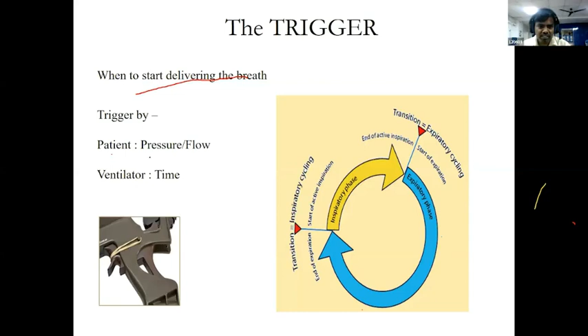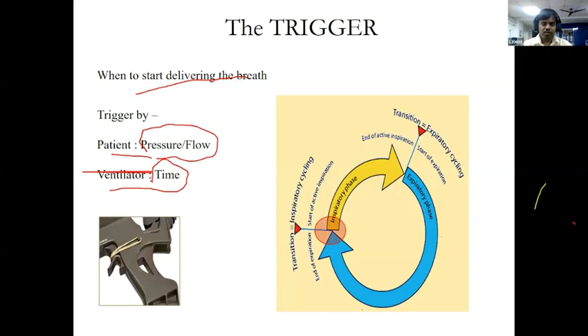So trigger by the patient depends on pressure and flow. For the ventilator, it depends on time. So 5 cycles will deliver 5 breaths according to the patient. The patient is triggering, the ventilator will deliver. Both should go in parallel, right? Yes. So this is about trigger.